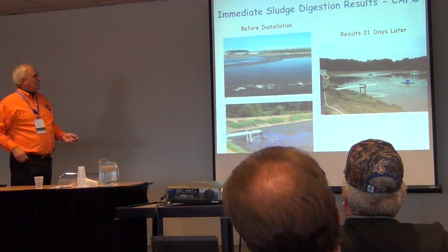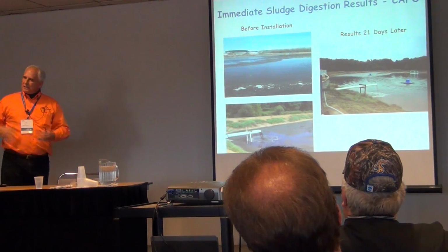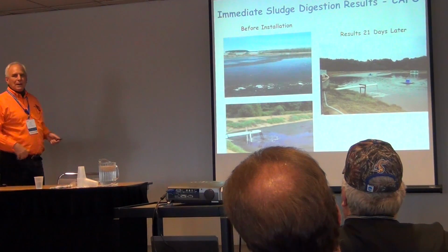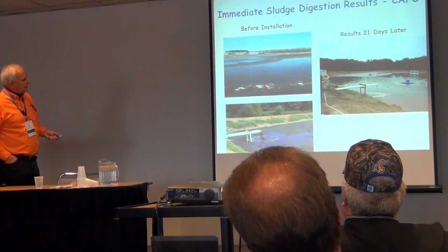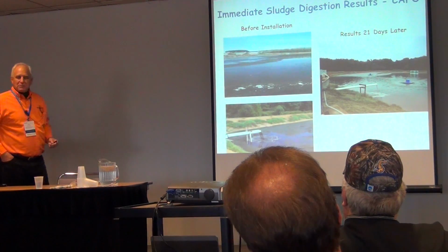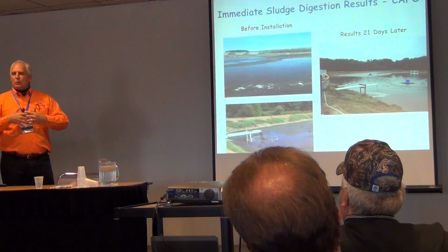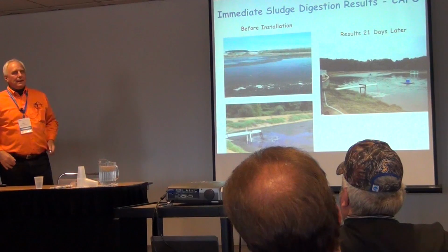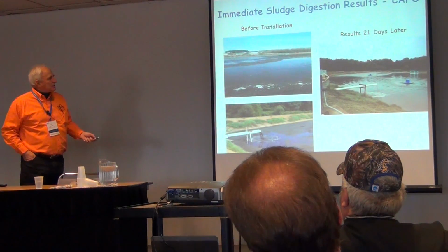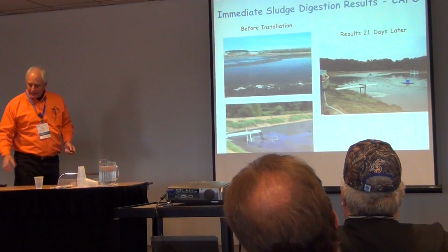Here's another picture of a different hog farm. You can see the sludge. There's no wind activity because the surface scum is so stabilized. You can even see some of it floating here. But look here. This is the water coming back from the barn before. But look over here. This looks like iced tea. And that's because the facultative bacteria population quintupled going through the flush alley. And you can see now that you've got this sweet layer because you can see the wind activity and the wave action.